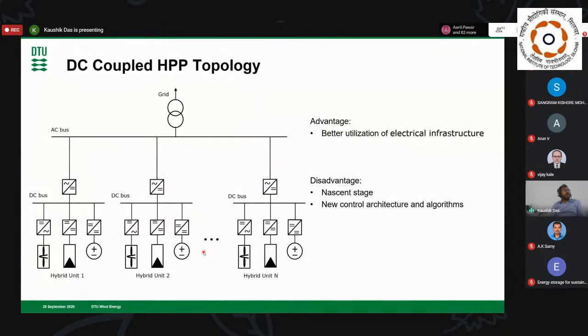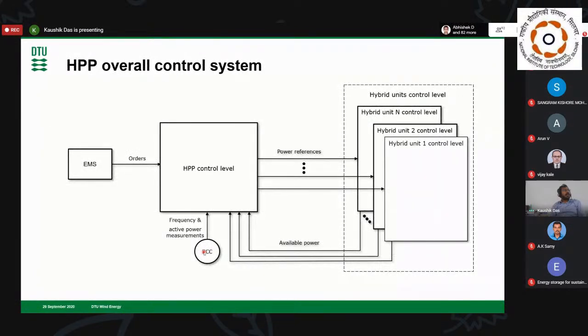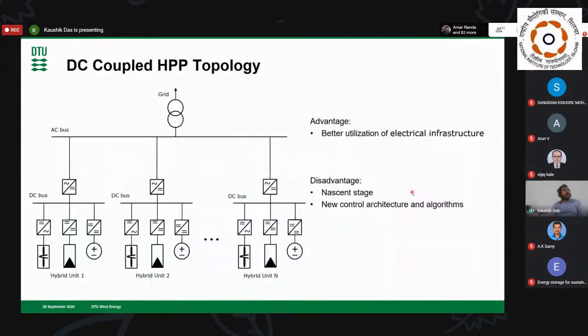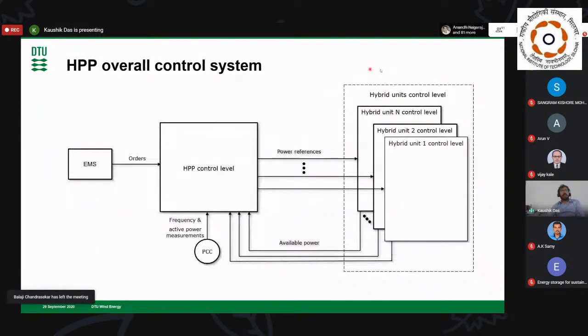Similarly, for the DC coupled topology, you have only one control level here - a hybrid power plant control - and you are directly talking to each inverter control of the hybrid system. So you are getting rid of all the intermediary control layers, which also increases the reliability of the system.